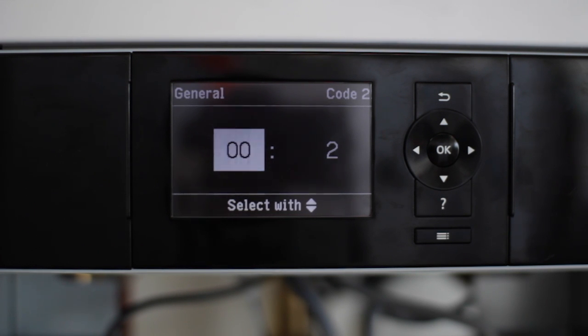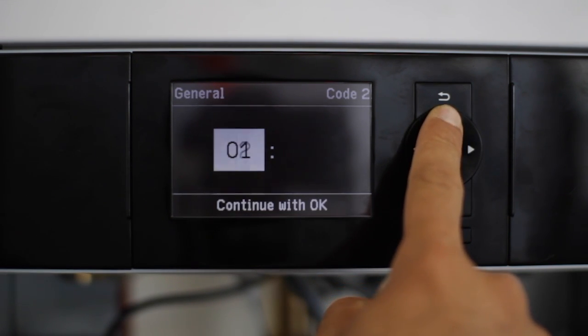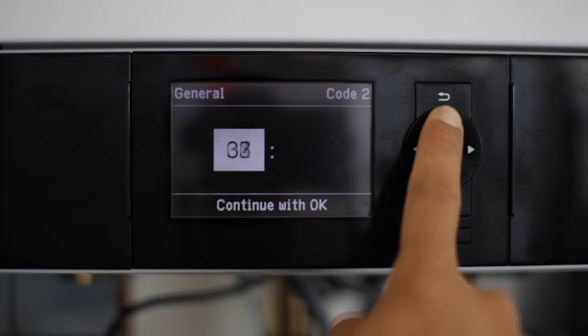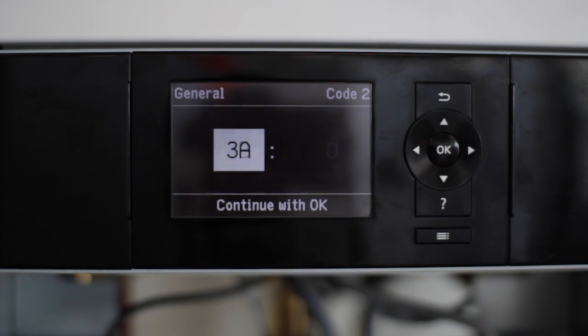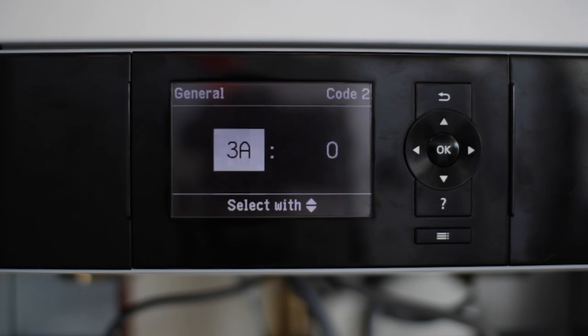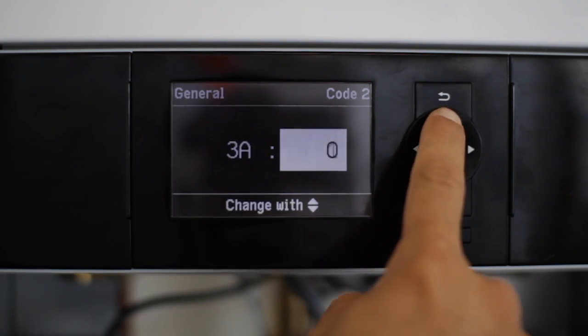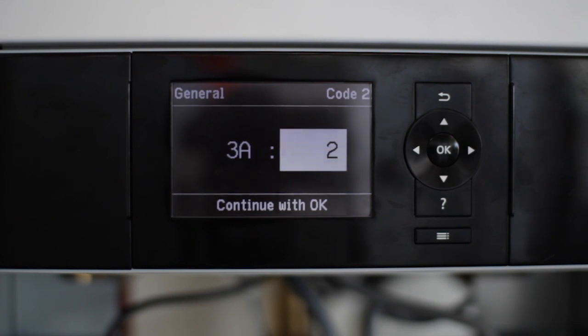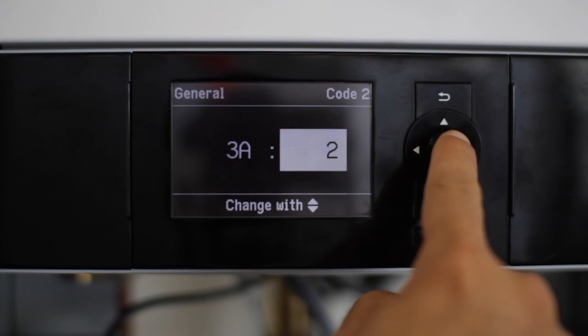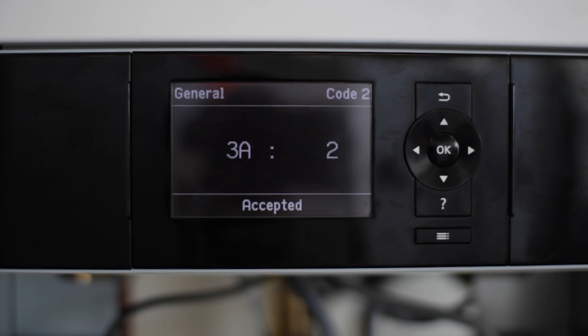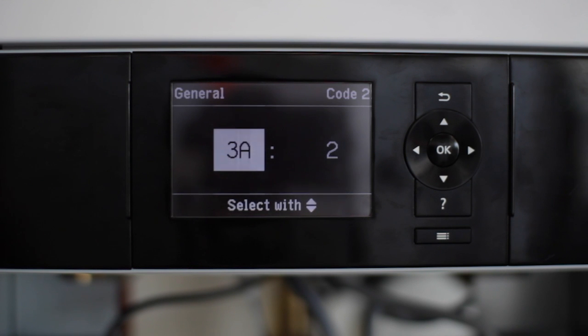So we're going to scroll to address 3A. 3A is associated to DE1. We're going to select the value of 2, which tells the boiler to activate DE1 for external demand. Once we've changed that to 2, we're going to hit OK. We should see Accepted below.